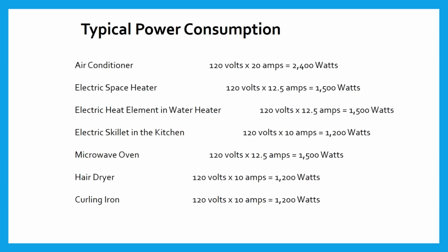Now, even if you've got one of the 50 amp 240 volt power cords, which gives you 12,000 watts, these are big rigs, so we may have 2 or even 3 air conditioners on the roof. So if you took that 2,400 and multiplied it times 3, I mean, my, look what happens. And then you add in maybe the electric heat element for the water heater. Add in maybe cooking in the skillet in the kitchen and running the microwave. So pretty soon what happens is we're pushing the limit even for the big power cords, because we're pushing the capacity of what's feeding this whole operation.